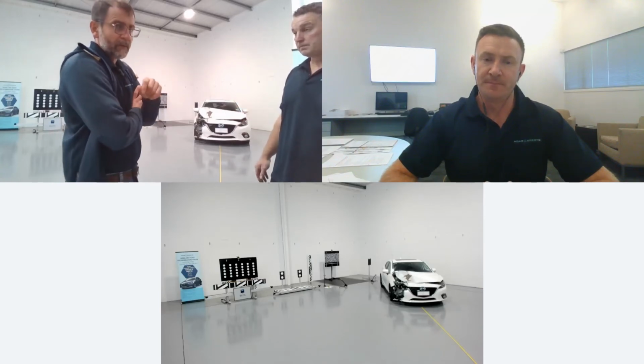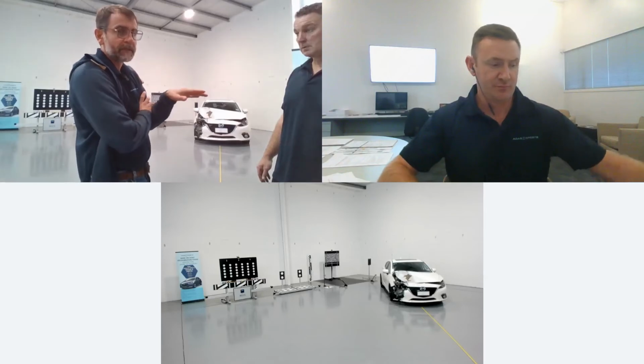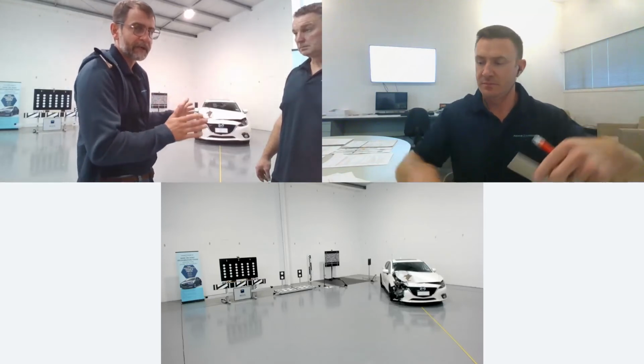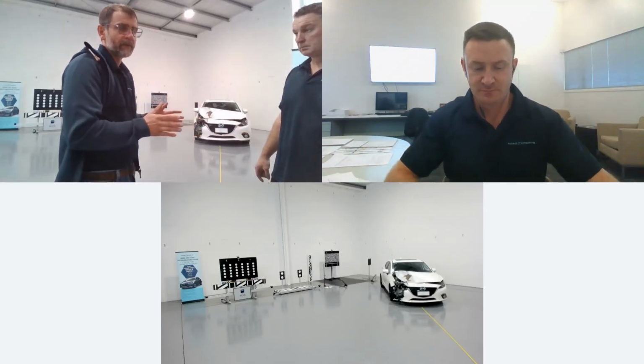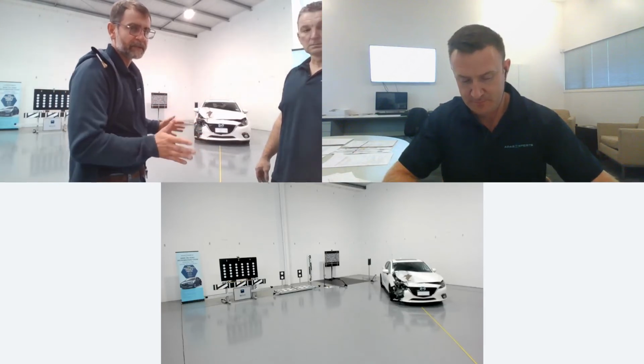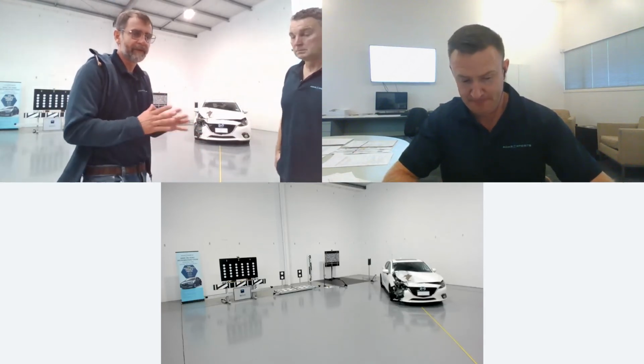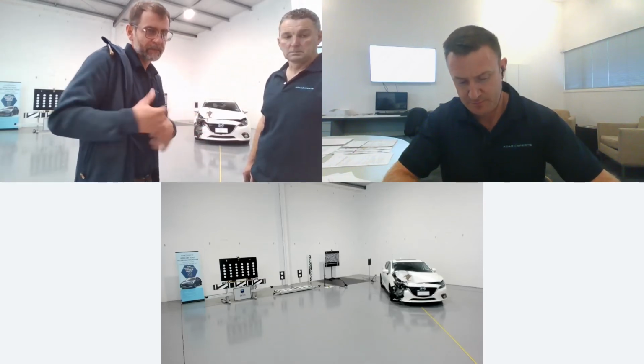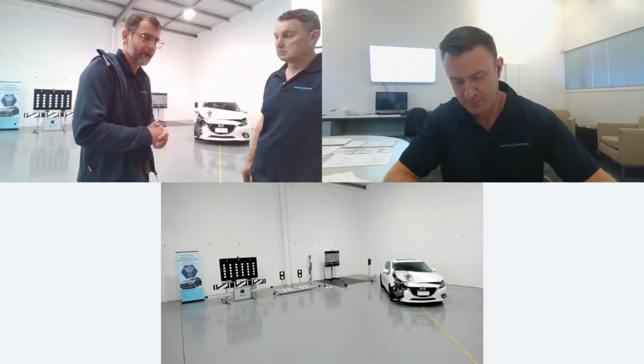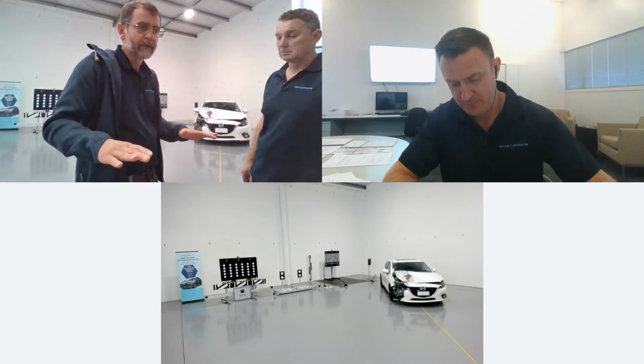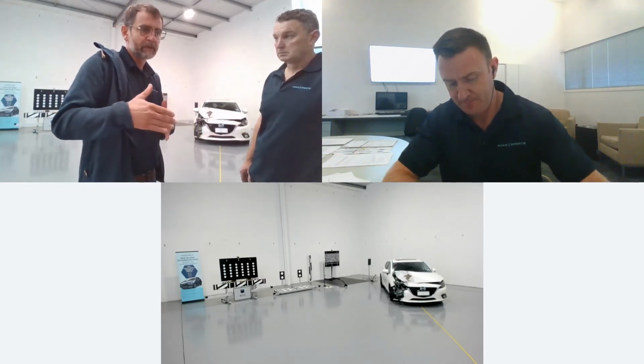Just a little bit more on top of that, he said something very important, that it's done in a correct space. So if you're calibrating blind spot, we really have that big space which needs to be completely open. So if you fail calibration, the first thing you want to have in your mind as a technician, because I'm a technical trainer, I'm looking from that angle now, is that you need to go with the method of elimination.